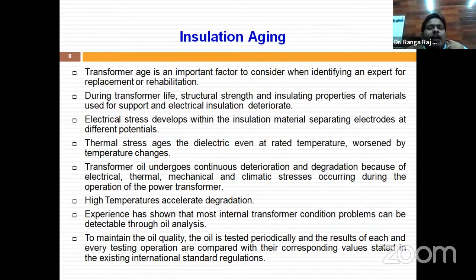The insulating material loses its operating performance - that is aging. There are different causes for aging; mainly 5 to 6 stresses degrade the operating performance of oil as well as paper. So how do these stresses develop inside the machine? That is the first thing we should know.